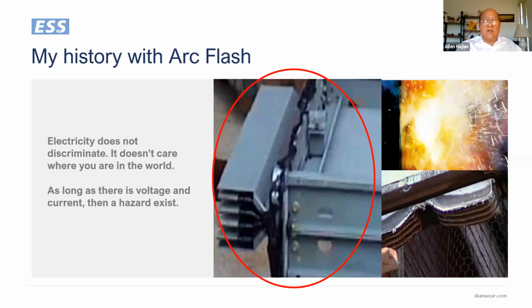So I went to our high powered lab, and an engineering manager, John Gregory, told me that he had been experimenting with arc flash and arc flash consequences and how to measure arc flash for NFPA 70E, and that NFPA 70E was coming out with recommendations for arc flash protection. So the fatality happened in October of 1999, and in October of 1999, the 2000 version of NFPA 70E was published. So it gave me a basis for developing a very robust electrical safety program that could be applied in US, in North America, and globally.